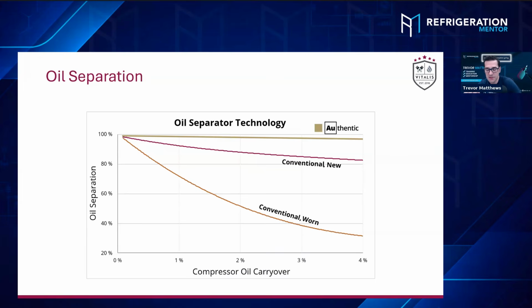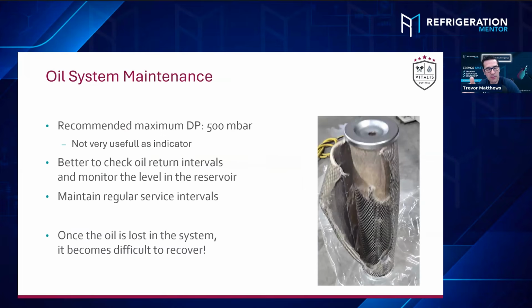Yeah, I know in my advanced service compressor master class, I trained compressors for years and years, and technicians are always surprised at the amount of detail you have to look into. It's not just that you pull off the head and look at it. There's so much uniqueness to each different compressor, and the things you've got to look for: scoring, rings and wrist pins. It does take work to do that, but like Jonas says, if you do this, you will find a root cause, and the next one's not going to fail. You know what I mean? Or shouldn't fail. That's the ideal scenario, yeah.